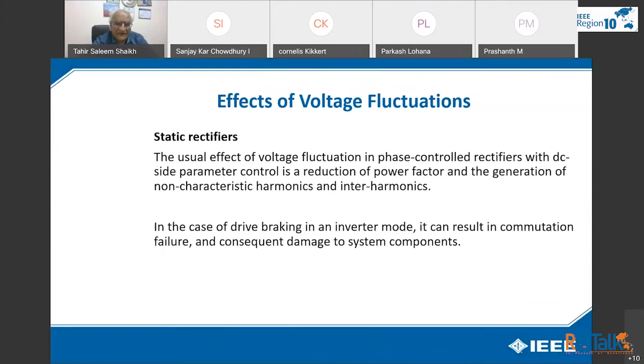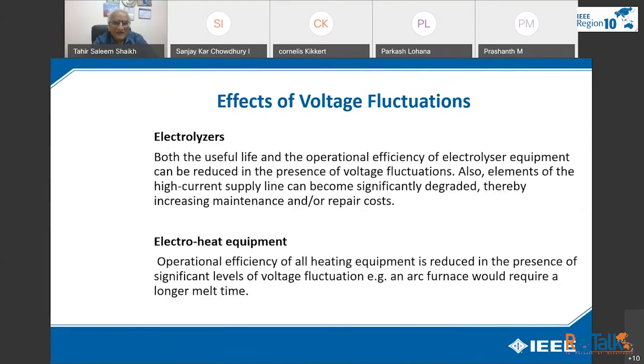Static rectifier: the usual effect of voltage fluctuation on a phase control rectifier with DC side parameter control is a reduction of power factor and the generation of non-characteristic harmonics and interharmonics. We come to it later on. In the case of a drive braking in inverter mode, it can result in commutation failure and consequent damage to the system components. Electrolyzer: both the useful life and the operational efficiency of electrolyzer equipment can be reduced in the presence of voltage fluctuation. Also, elements of the high current supply line can become significantly degraded, thereby increasing maintenance or repair cost. Operational efficiency of all heating equipment is reduced in the presence of a significant level of voltage fluctuation. For example, an arc furnace would require a longer melt time.